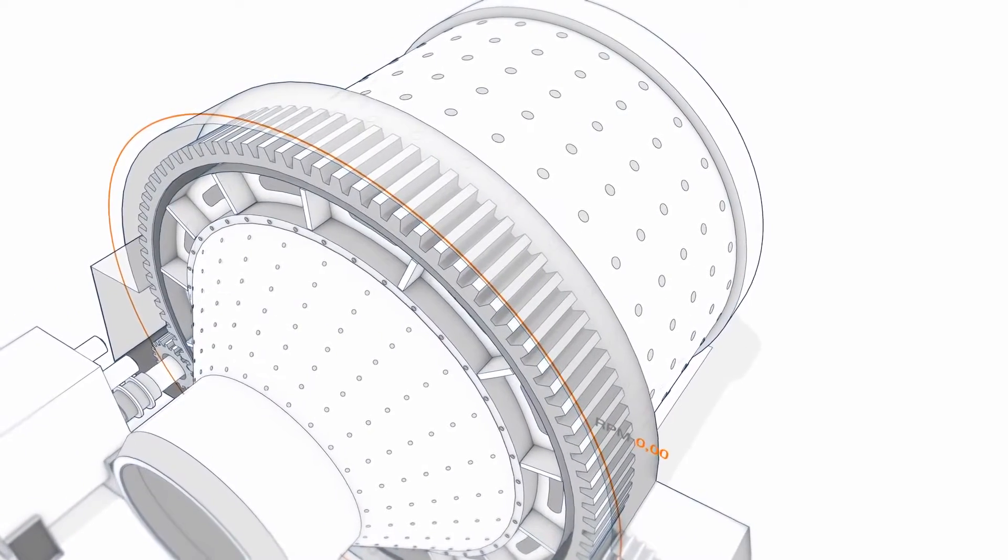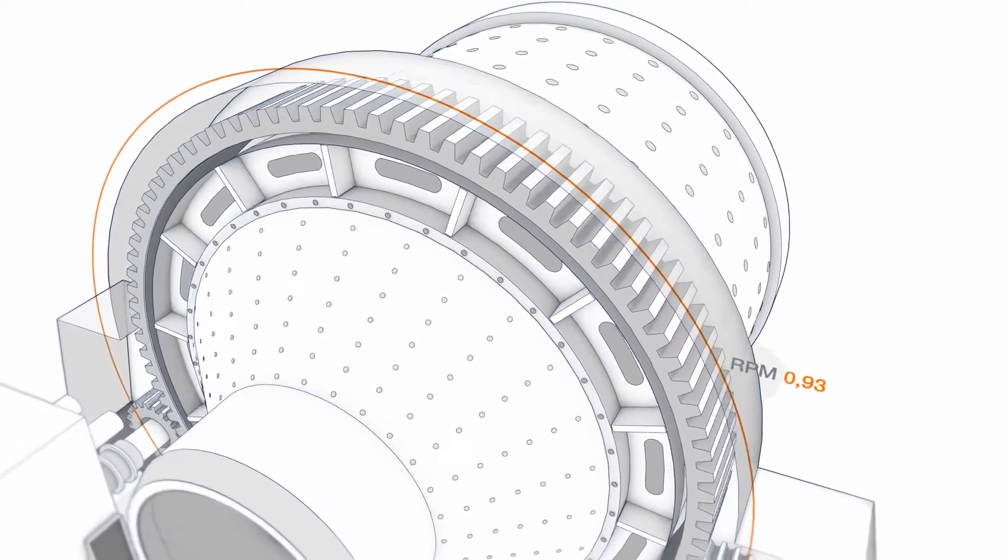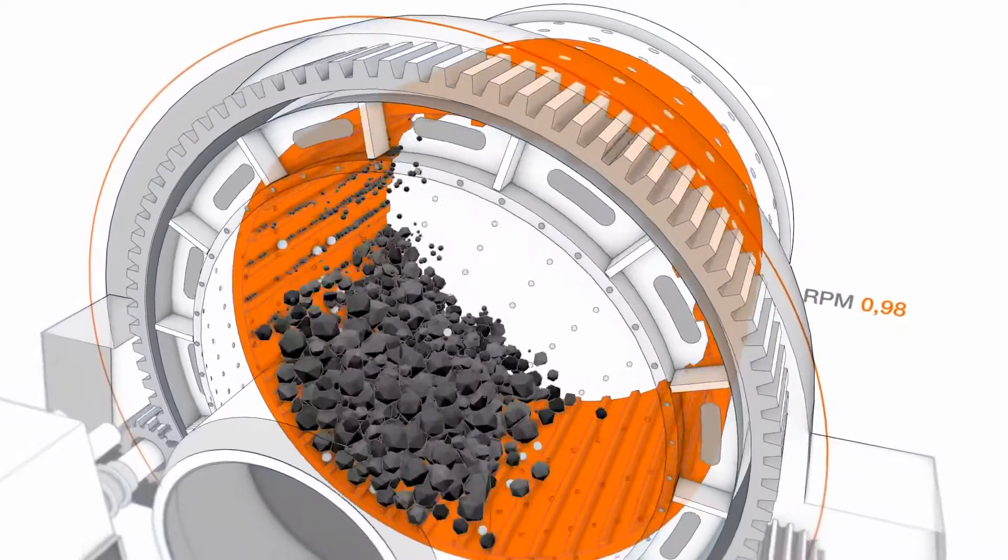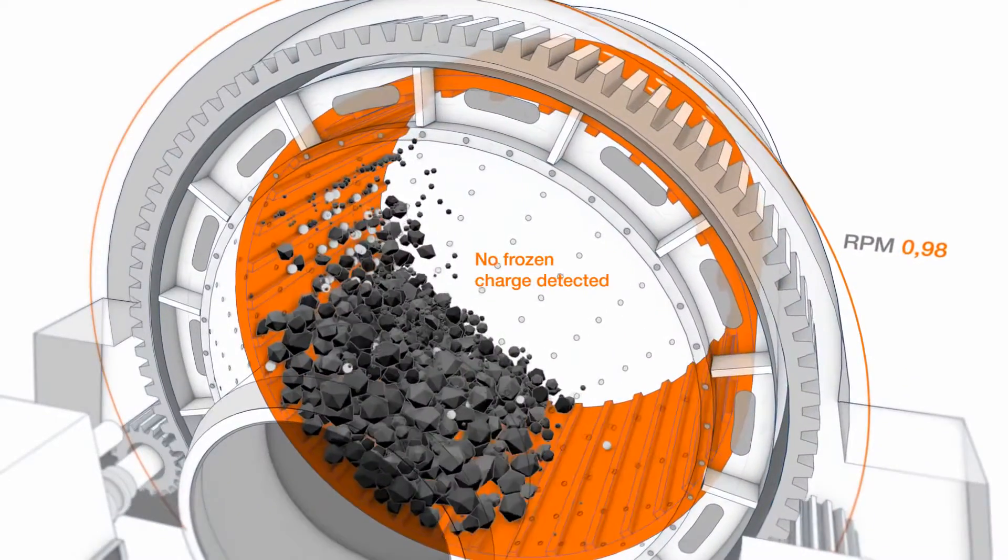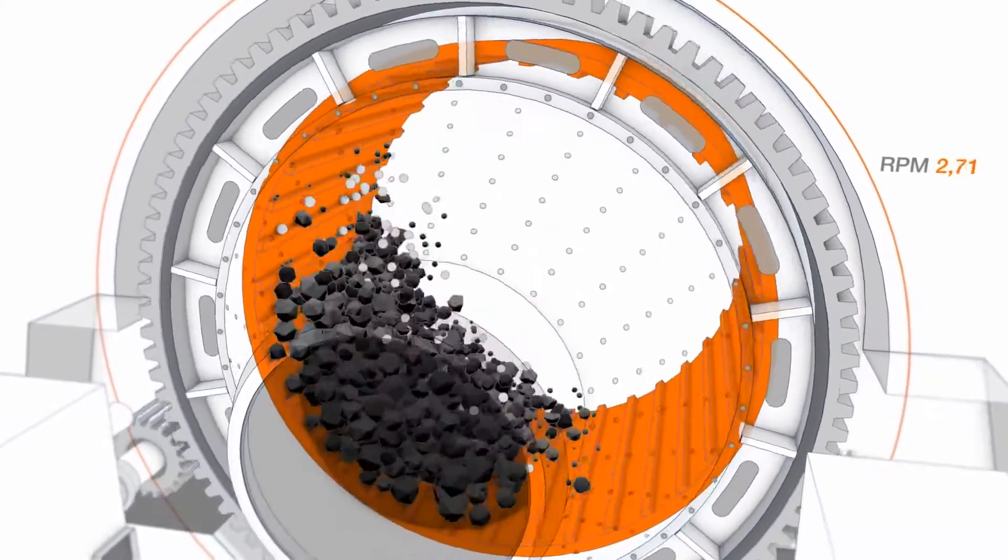The mill starts moving slowly in a frozen charge detection mode. Once the ore input successfully cascades, the drive releases the mill to normal operation and it accelerates to nominal speed.